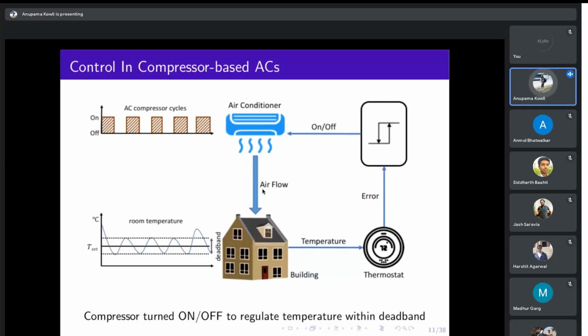And so this is what leads to this sort of an AC duty cycle, right? As long as your internal air temperature continues to be above the reference point you have given, the compressor is going to be on. As soon as you are below a particular dead band outside of this 22, so let's say you keep pumping in cooled air, your temperature keeps dropping and it reaches 21 degrees Celsius. At this point, you have overcooled the system, at which point the compressor is going to turn off, and then it turns on again, it turns off. And this is what you see. Your temperature effectively starts getting regulated within a tight band around that 22 that you wanted it to get regulated at. Everybody clear up till this?